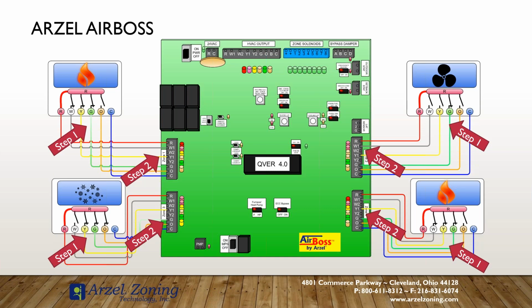So if my heating call comes in first, it's served for 20 minutes and then it'll switch to the opposing call. But the panel will never output for heating and cooling at the same time. It will only ever output for one or the other, opening or closing the zone dampers appropriately based on whether it's serving that heating or cooling call.